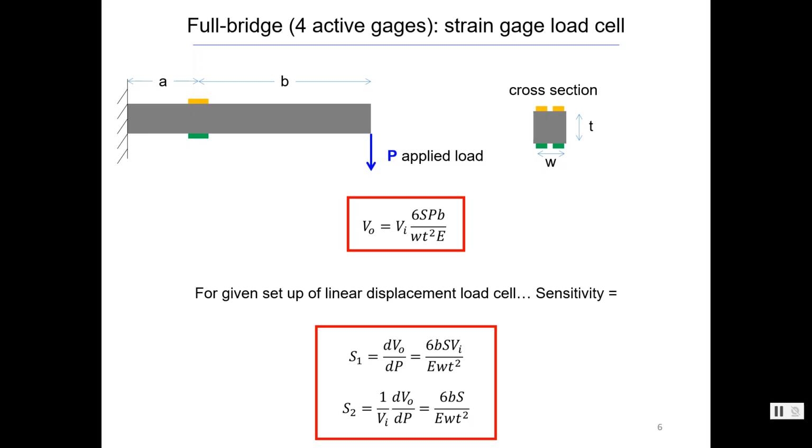For that to work, we would have to go through a calibration process. So that would be the first phase of the lab. We would set known weights on the end of this. We would measure the output voltage for those different weights. And then through that, we can get a sensitivity. And we would apply that sensitivity, apply a zero offset. So we zero out our strain gauge and we apply sensitivity. So our output is not in volts or millivolts, but it's in pounds force, because here in America, the tippet is rated in pounds.